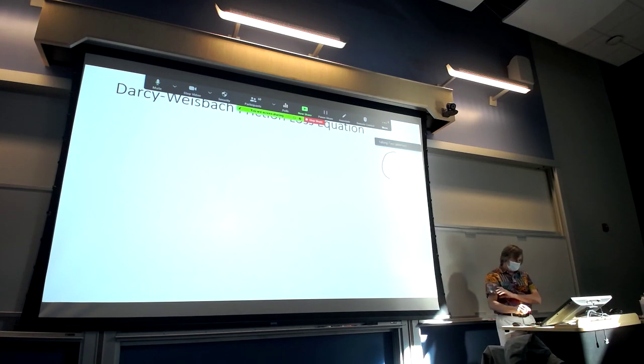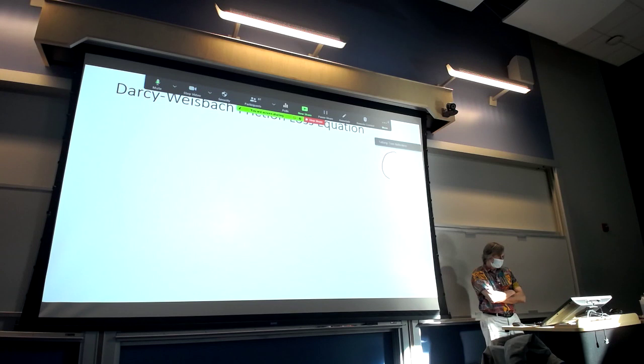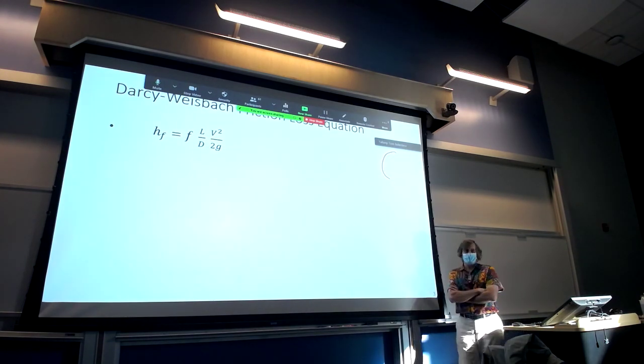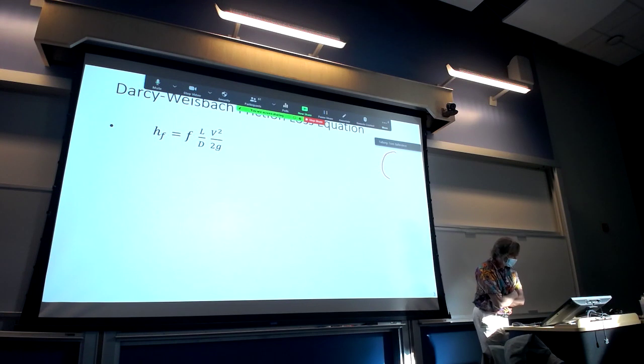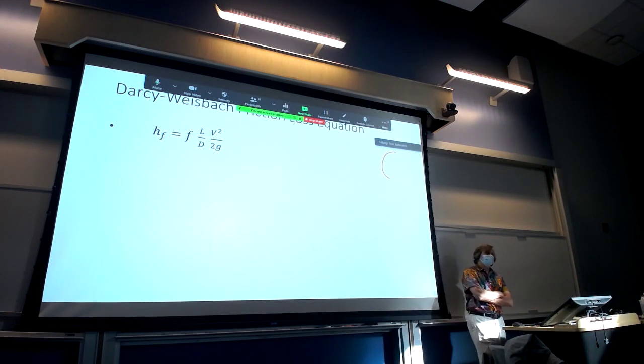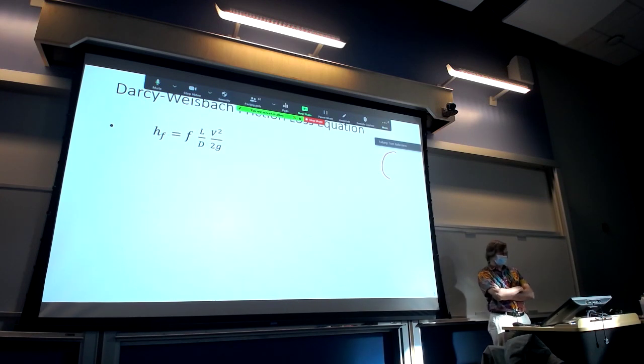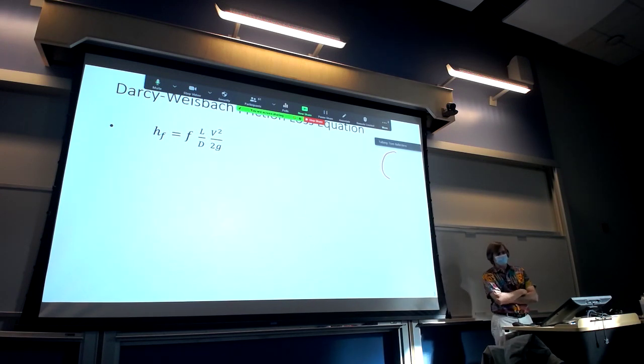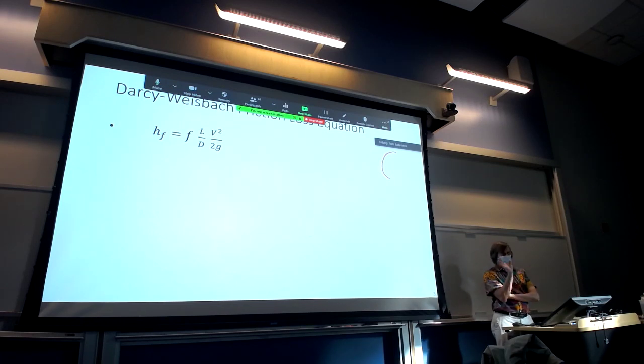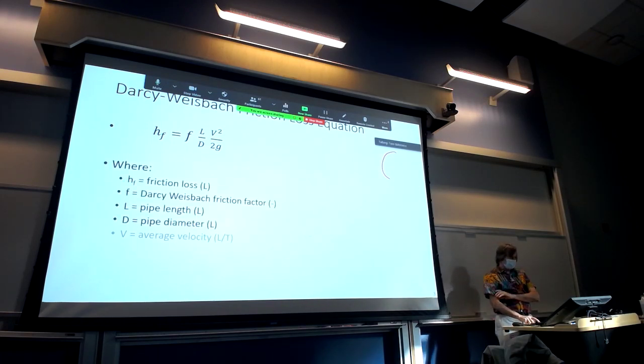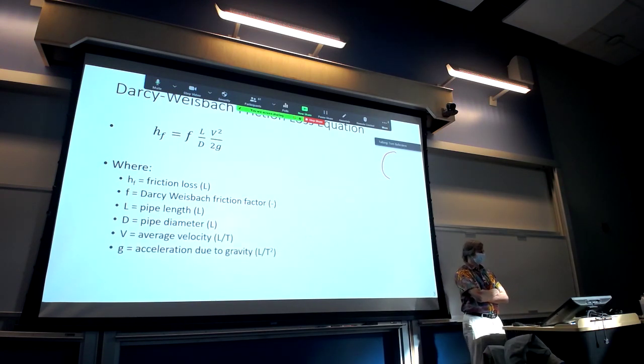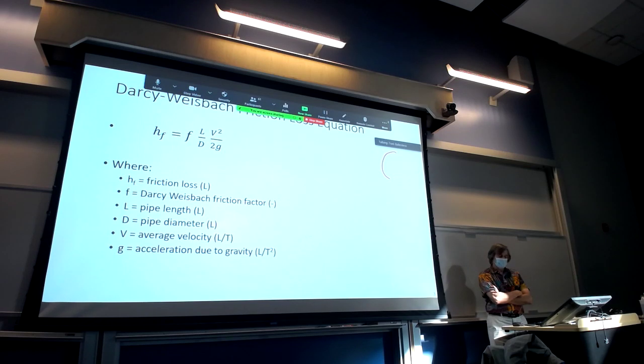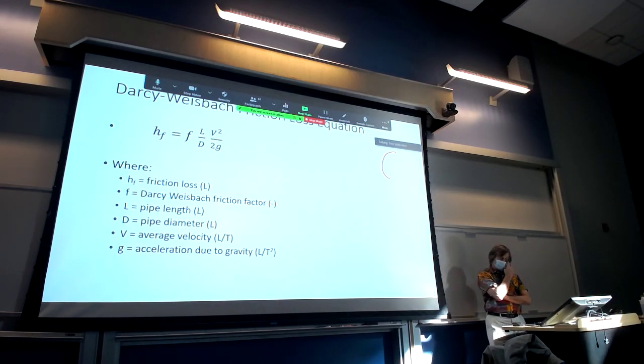The Darcy-Weisbach friction loss equation is what we're using for friction losses. Next class, we'll talk about another equation that some faculty at this university and colleagues at other universities use. Darcy-Weisbach is the dominant equation for pipe friction losses used all over the globe. We can calculate the friction loss — the component in the energy balance equation — if we know all the terms on the right-hand side.